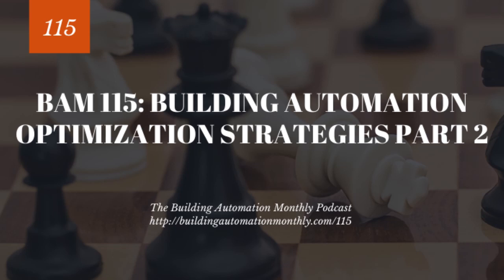And if it doesn't, you could do this a couple different ways. You could do this by averaging. You could put DP sensors in multiple different spots and average that. That's one way. You could do this by putting it into a place where you have a diversity of box types. You can do it multiple different ways. The important thing is to not let a DP sensor sit with a 200 CFM box when you've got 20 boxes that are 1,000 CFM.